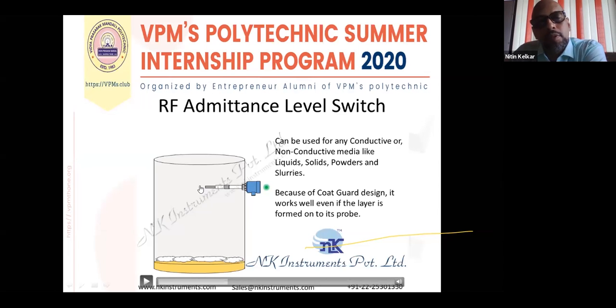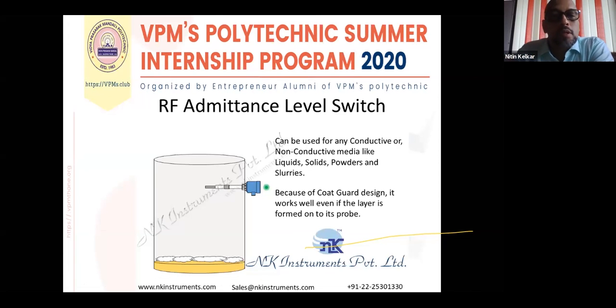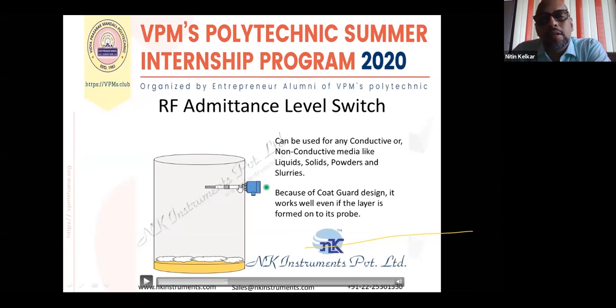At the same time, if the medium is sticky, it will form a layer, and this layer formation will keep the switch continuously on even if the tank is empty. The level switch will show that the tank is full, and it will give us a wrong signal basically. To avoid that, we have added one more probe into it.